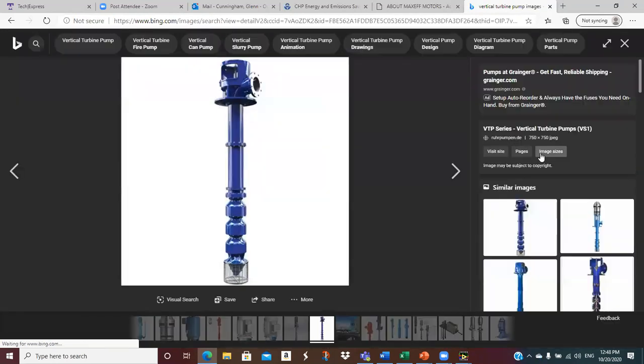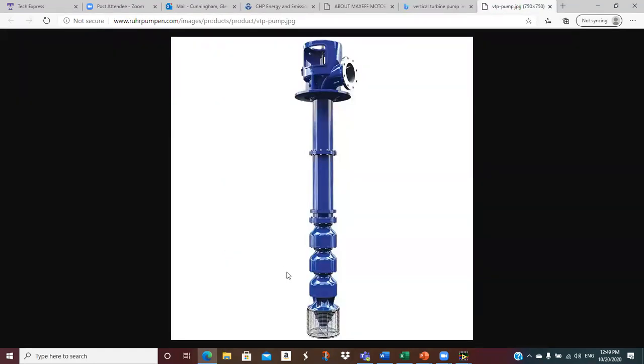Let's see. There you go. So your motor mounts up here on top of it, and this flange mounts on a concrete deck, and then this shaft extends down. I mean, some of these things, this shaft could be really, really long. Now, the typical one might be 10 to 20 feet. And it sticks down into this well, and each one of these, they call them bowls. This would be a 3 impeller situation. So this would be like a 3-stage vertical turbine pump, something like that.